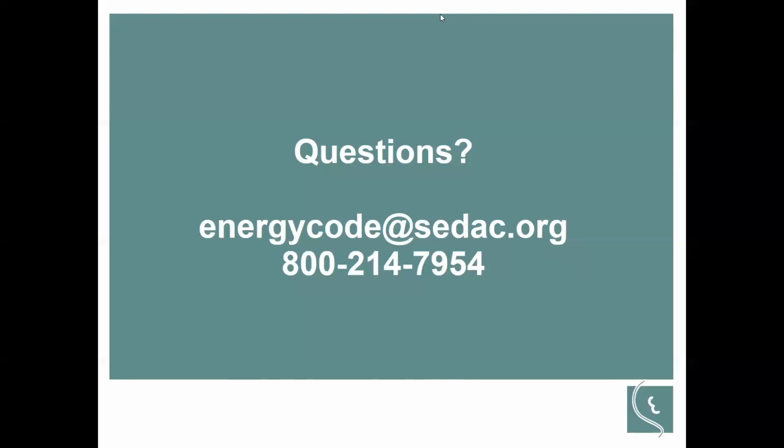And another question: what are the requirements for partial renovation, such as lighting or HVAC? Renovations are covered under sections 500 and 600. That requires that whatever equipment you are replacing meets the standard for new construction. So if you are going to replace your heating system, that new heating system would have to be compliant. But if you are just replacing a furnace, you don't have to go back and retest your ductwork and other provisions that are not affected by the specific item that you are working on.